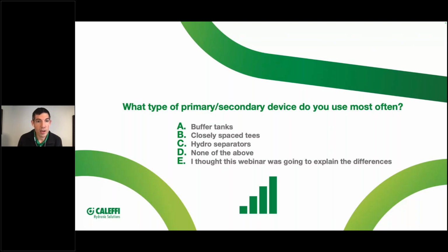So we ended up with 20% buffer tanks, 39% closely spaced T's, 24% hydro separators, 2% none of the above, and 15% you're supposed to tell me, which is completely fine. So we'll go on and go through those first three. All three of those are perfectly acceptable ways to do primary, secondary piping. We'll kind of do the pros and cons as we go through.